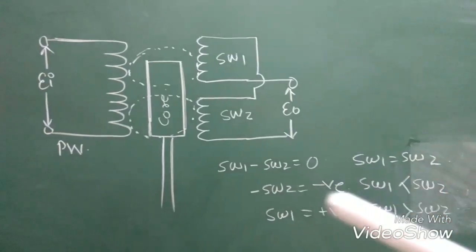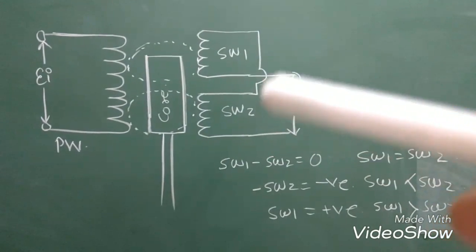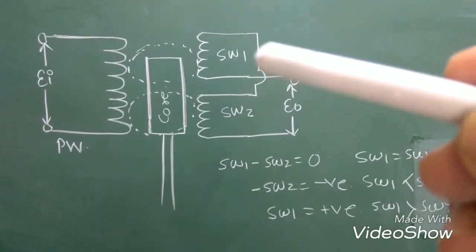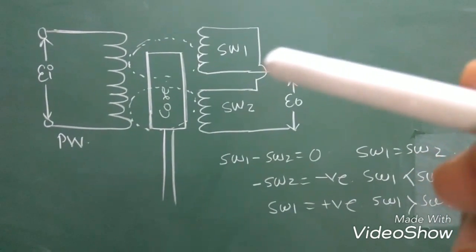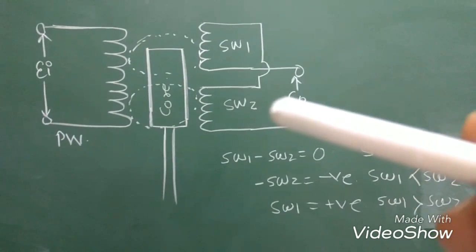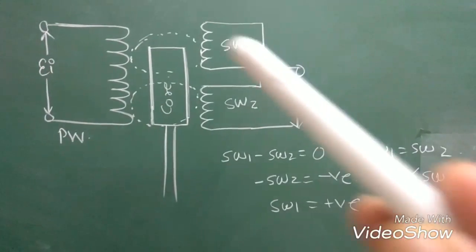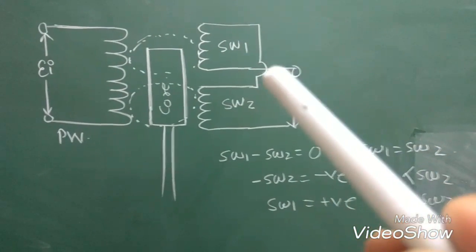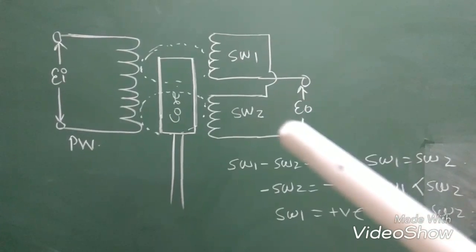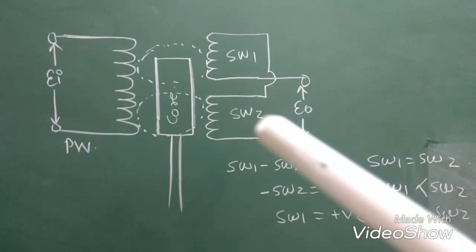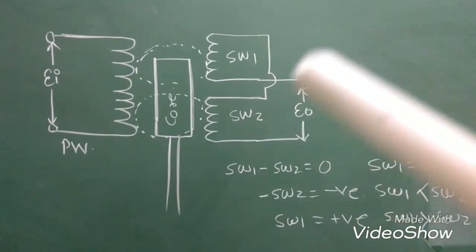Now, in this LVDT, we are having two different secondary windings — secondary winding 1 and secondary winding 2. A few conditions need to be satisfied. First, these two windings, secondary winding 1 and secondary winding 2, must be connected in series. You can see secondary winding 1 is connected with secondary winding 2 in series, and here we are getting the output voltage. Second condition: they must have equal number of turns. The total number of turns on secondary winding 1 must be equal to total number of turns on secondary winding 2.